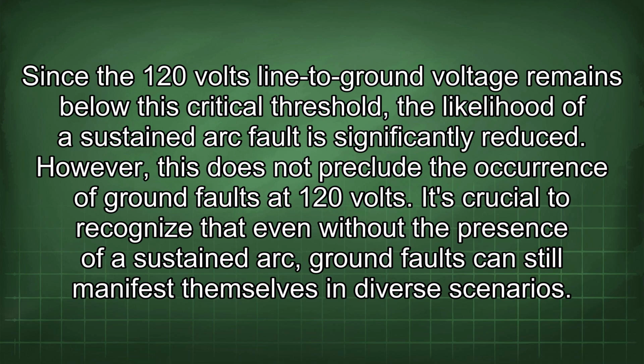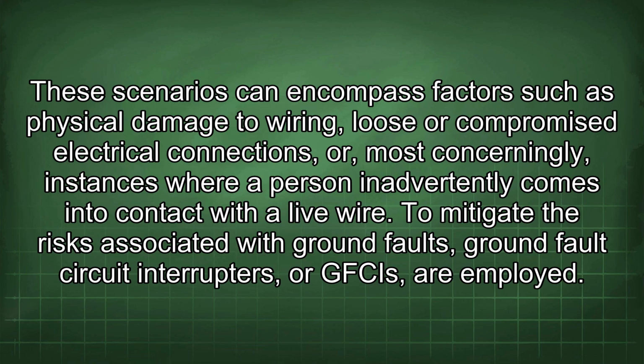However, this does not preclude the occurrence of ground faults at 120 volts. It's crucial to recognize that even without the presence of a sustained arc, ground faults can still manifest themselves in diverse scenarios. These scenarios can encompass factors such as physical damage to wiring, loose or compromised electrical connections, or, most concerningly, instances where a person inadvertently comes into contact with a live wire.